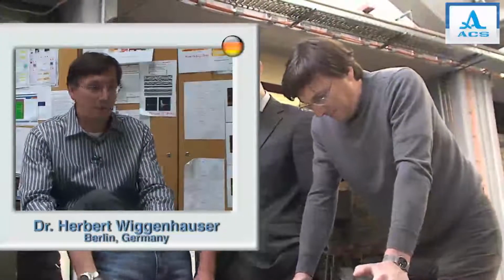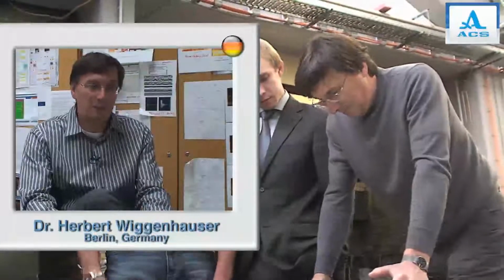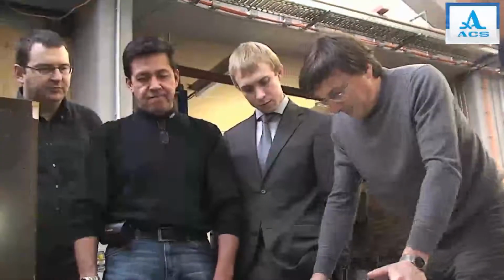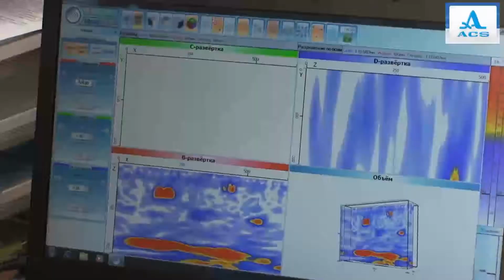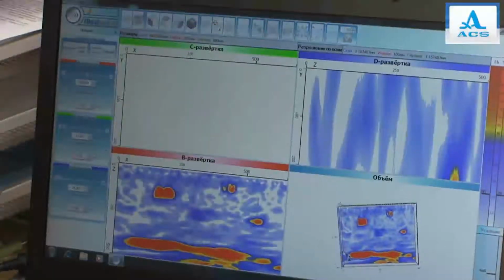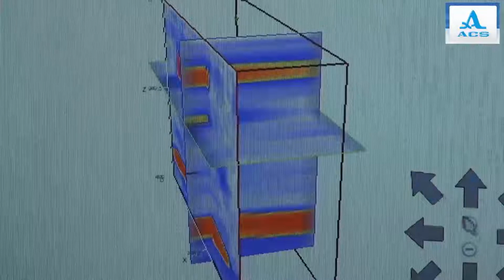First of all, it's an imaging system. You get an image of the interior of concrete practically in real time after you do measurements. The axonometric image reconstruction makes it possible to readily discern internal flaws. It could be more evident only if the concrete would have been turned into glass.